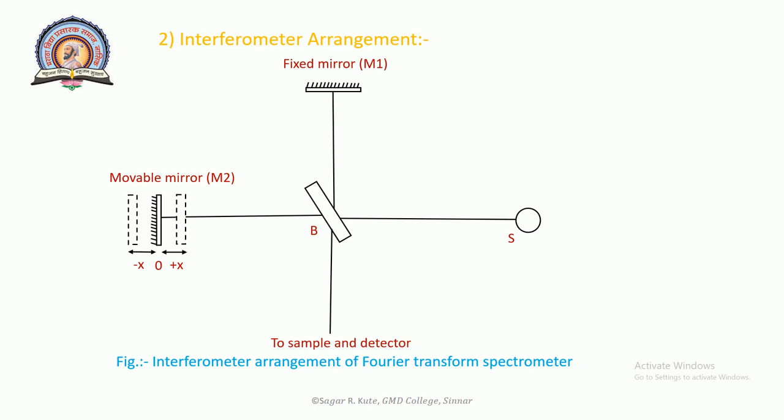Second will be the interferometer arrangement. This diagram shows interferometer arrangement of Fourier transform spectrometer. The basic components of Fourier transform spectrometer are given in figure. The source is usual glower operated at very high temperature. The Michelson interferometer consists of source S, beam splitter B, and plane mirrors M1 and M2. The mirror M1 is fixed and M2 is capable of movement. The beam splitter allows 50% of radiation to mirror M1 and other 50% to mirror M2.